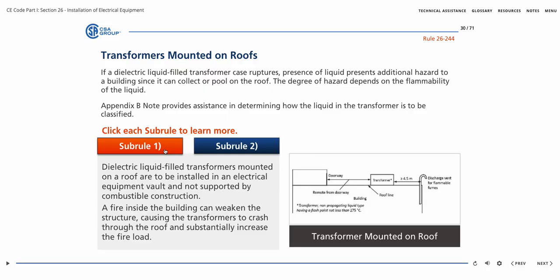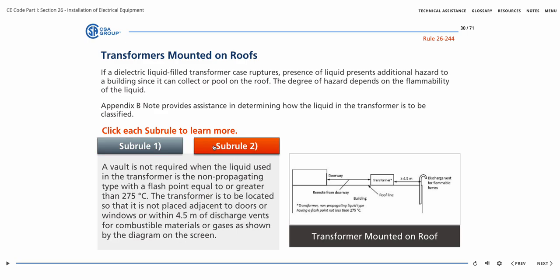Subrule 1 requires that dielectric liquid-filled transformers mounted on a roof are to be installed in an electrical equipment vault and not supported by combustible construction. The rationale is that a fire inside the building can weaken the structure, causing the transformers to crash through the roof and substantially increase the fire load. Subrule 2 states that a vault is not required when the liquid used in the transformer is the non-propagating type with a flash point equal to or greater than 275 degrees Celsius. The transformer is to be located so that it is not placed adjacent to doors or windows or within 4.5 meters of discharge vents for combustible materials or gases, as shown by the diagram on the screen.